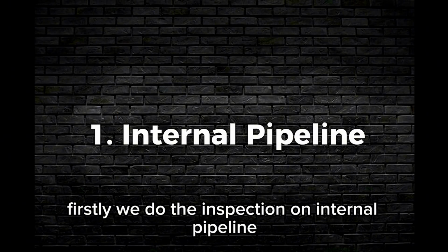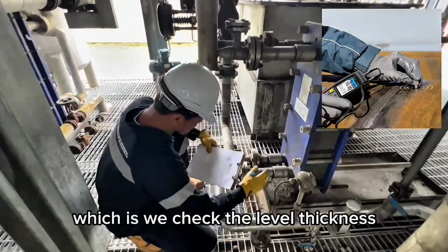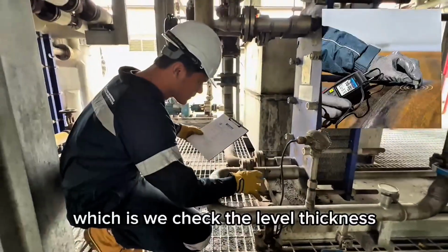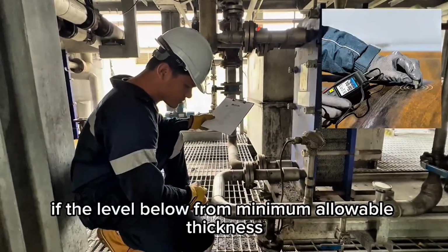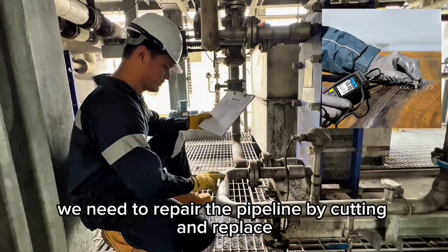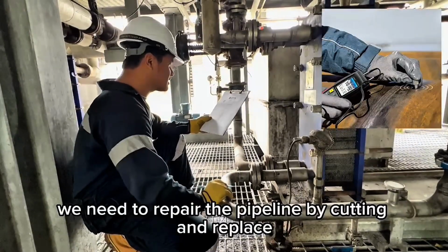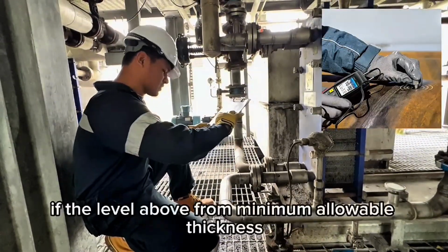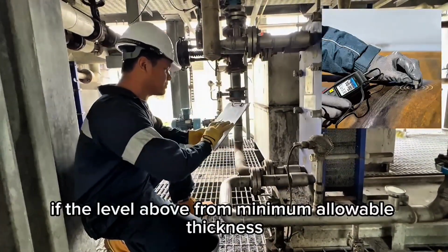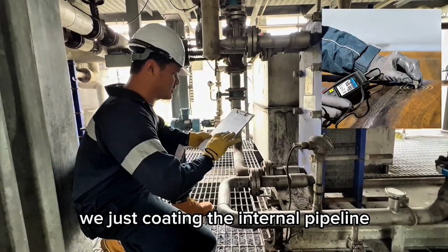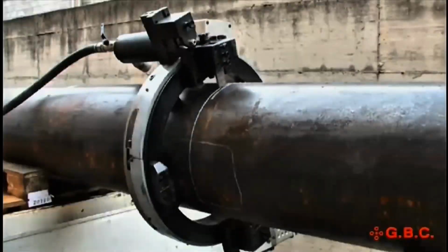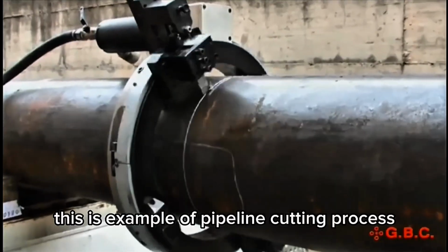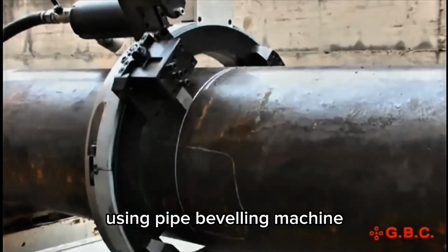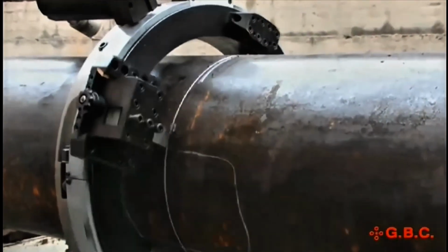Firstly, we do the inspection on the internal pipeline, which is we check the thickness level. If the level is below the minimum allowable thickness, we need to repair the pipeline by cutting and replacing it with a new pipeline. If the level is above the minimum allowable thickness, we just continue using the internal pipeline. This is an example of the pipeline cutting process using a pipe beveling machine.